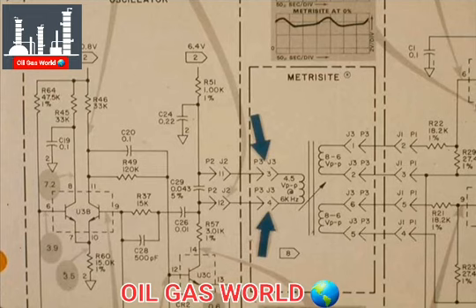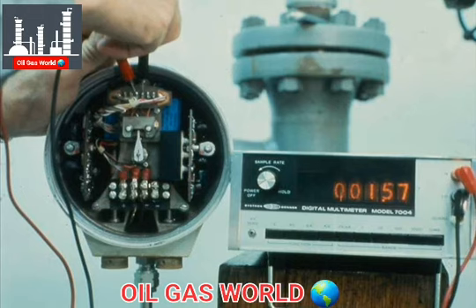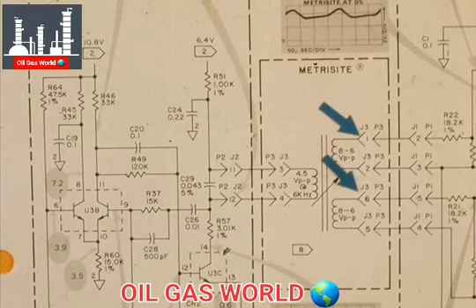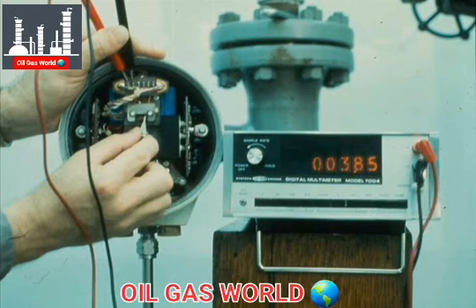For instance, check the oscillator by placing an AC voltmeter across pins 3 and 4 of jack 3. You should read approximately 1.6 volts AC on this voltmeter. Check the Metrisite by measuring the voltage at the secondary winding outputs, jack 3 pins 1 and 2, and jack 3 pins 5 and 6. The voltage should be between 6 to 8 volts peak to peak, depending on where the Metrisite is located. Move the Metrisite. The AC voltage should vary between 2 and 4 volts on this meter. If it doesn't, replace the Metrisite assembly.